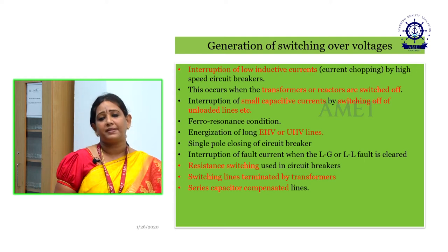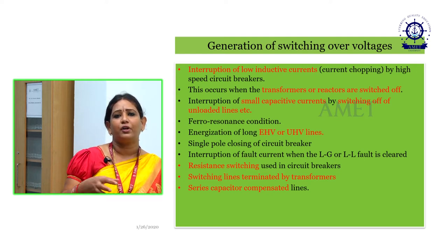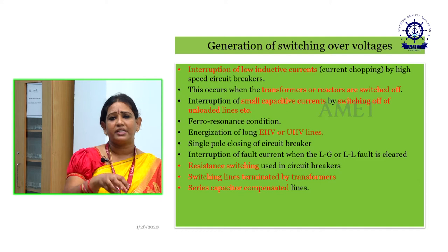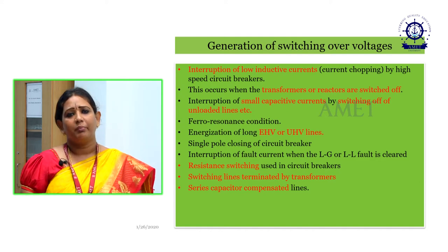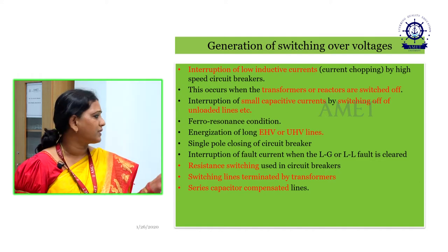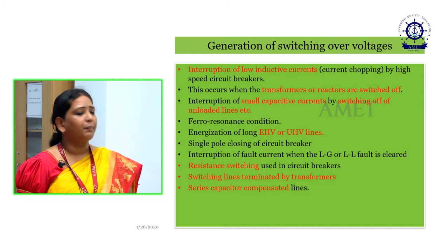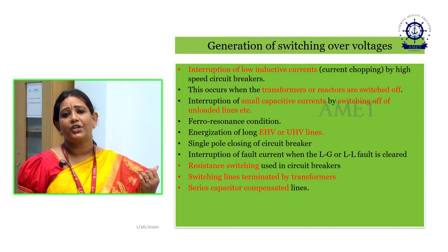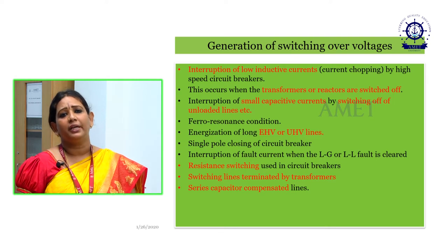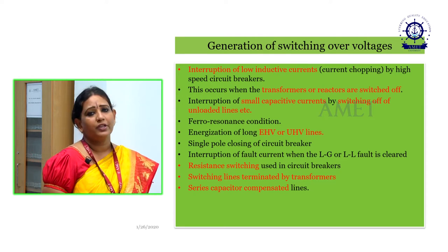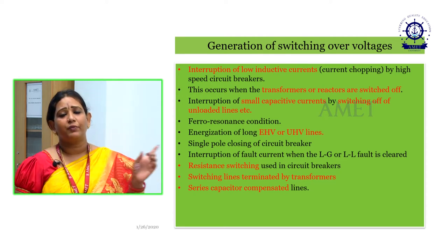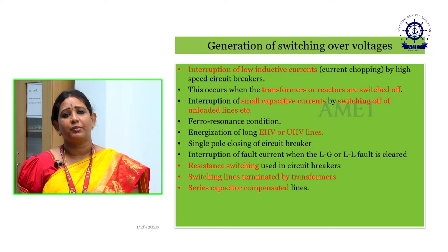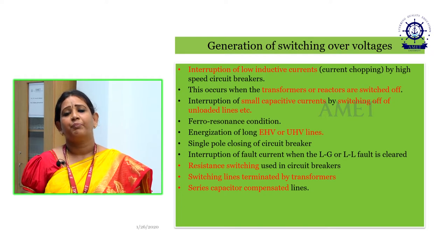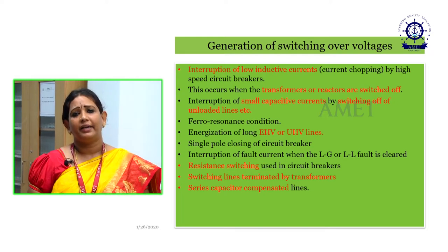Then series capacitor. We basically use the capacitor for boosting up the reactive power, that is, we are injecting reactive power into the system to maintain the balance of the transmission system. So series capacitor compensated lines are one of the reasons for generation of overvoltages, because series capacitor and shunt capacitor are very vital in a transmission system. We want to maintain the power balance, we basically go for it, and that leads to generation of overvoltage.